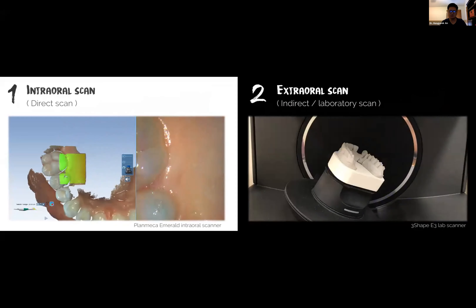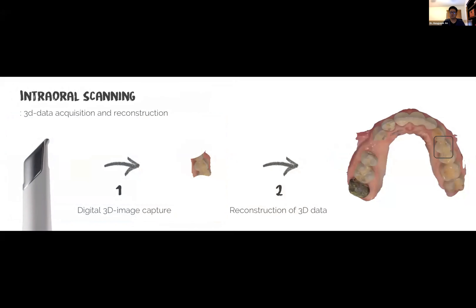Today we'll focus on intraoral scanning. The way an intraoral scanner works is simple: at the tip of the scanner, it continuously takes small three-dimensional pictures — that's step one, three-dimensional image capture. The tip is very small, so you can't capture the whole mouth at once. Those small pictures are sent to the computer, which takes about 10 to 25 pictures per second, then puts those pictures together to create a full-arch scan. That's step two: reconstruction of three-dimensional data.